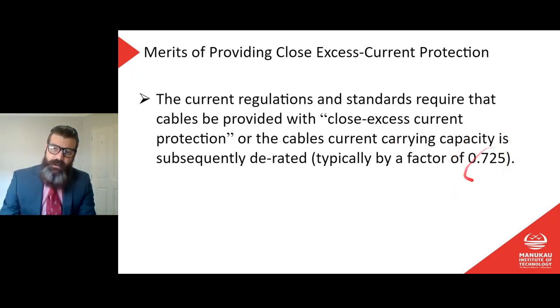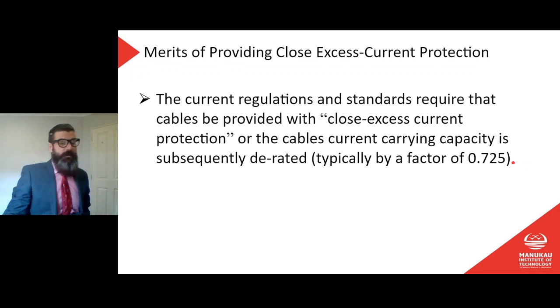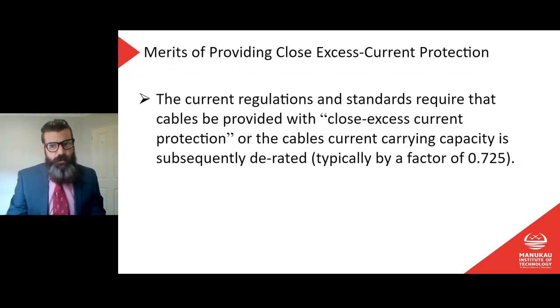So what that's saying is that if we do not provide a cable with close excess current protection, then we have to derate the cable. Why? Because we're going to allow a pretty high overcurrent to flow through that cable for quite some time before the circuit breaker or fuse trips if we're using coarse protection. So now we have to use a bigger cable. We'll derate the cable by a factor of 0.725.